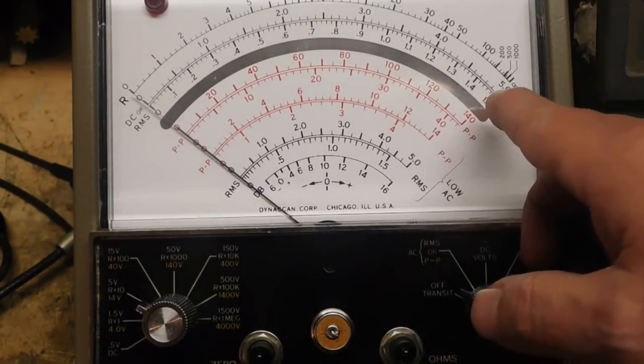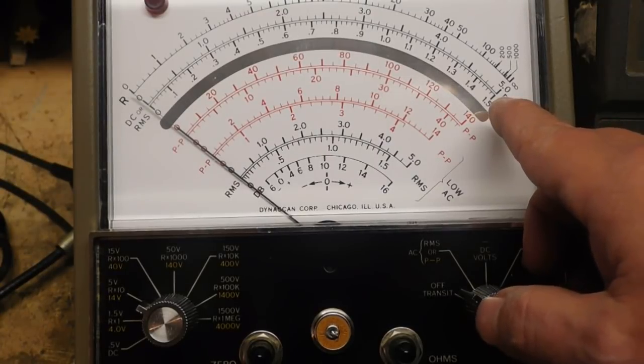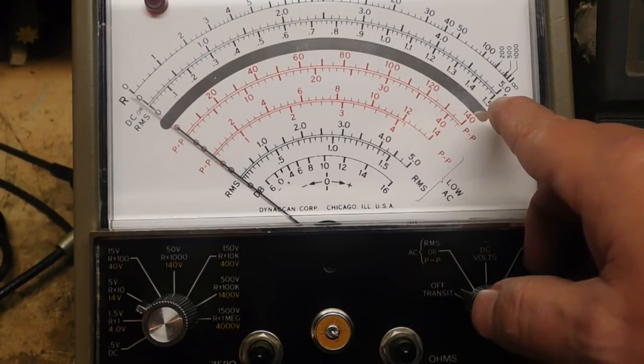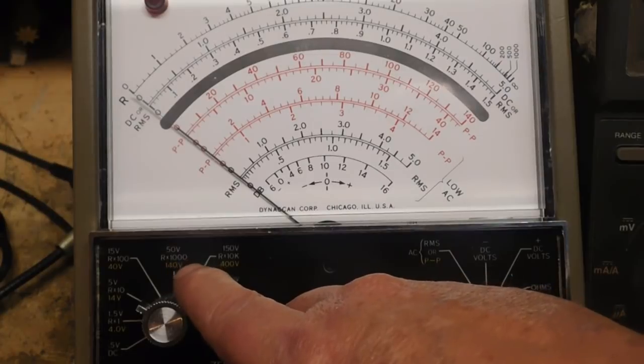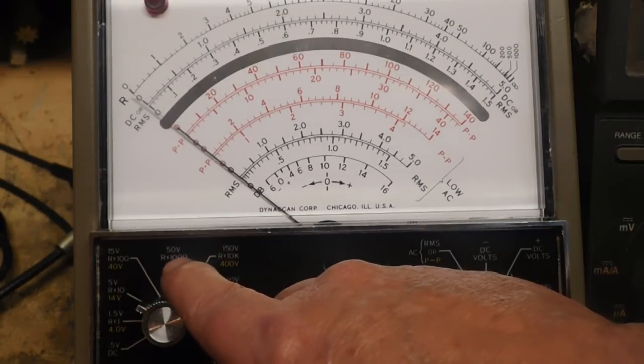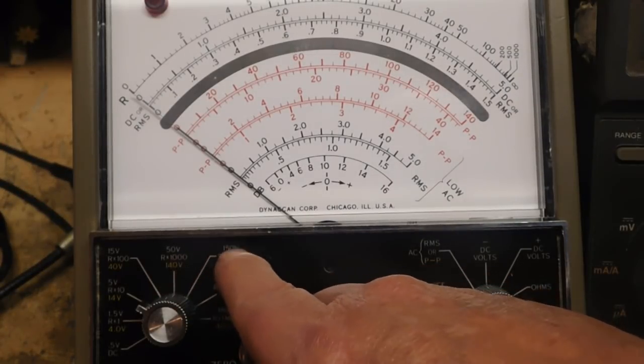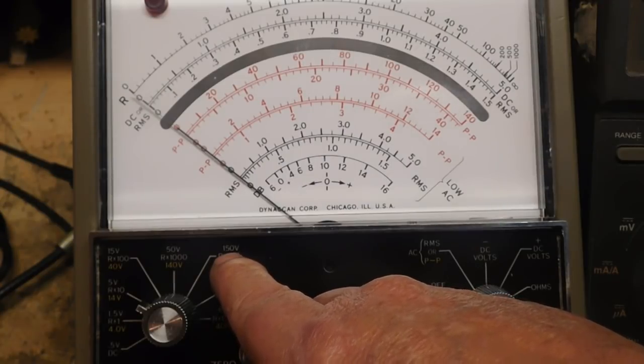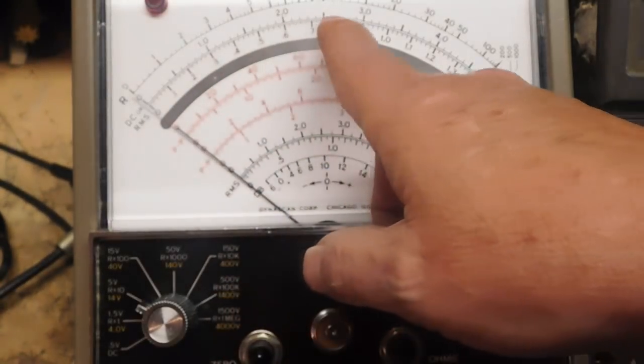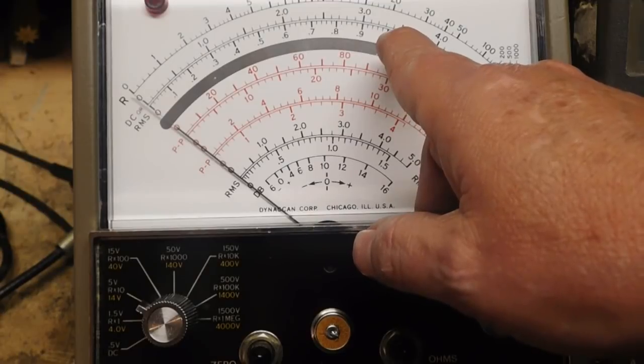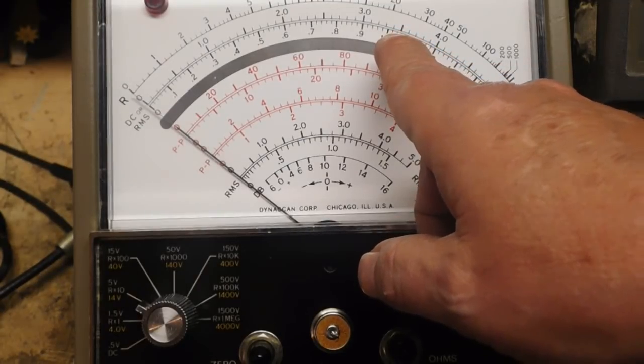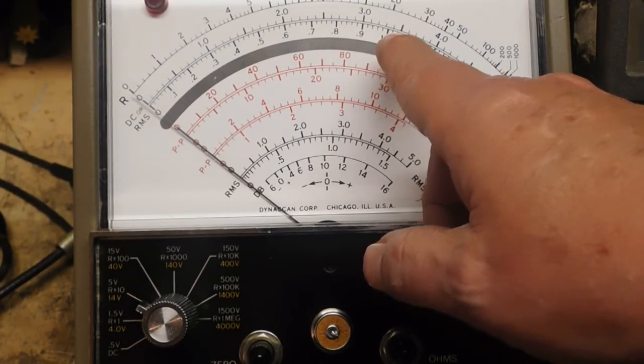So if I wanted to measure something that's 100 volts DC, the low scale below that is 50 volts, that's too low, so I'd want to set it for 150. The meter would then come up to the 1.0 here. Take that times 100, that's 100 volts.